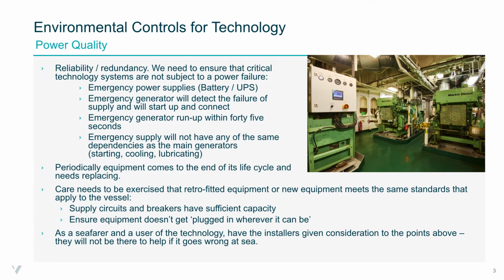and equipment shouldn't just be plugged in wherever it can be fitted. Now, the reason I raise this point is in discussions with seafarers, it's something that you do often hear about, where a new piece of equipment has been installed or a piece has been replaced, and due to an inconvenient siting of the legacy piece of equipment, the equipment's been relocated, and you do hear about stories where someone has fitted a flexible cord and a plug and plugged that piece of critical navigation equipment into a power point that used to be used for the kettle.